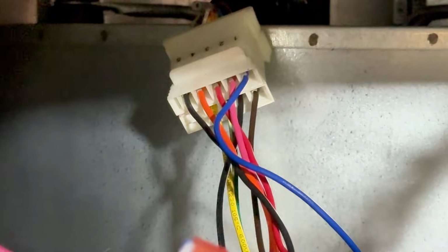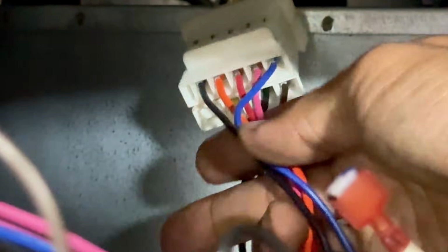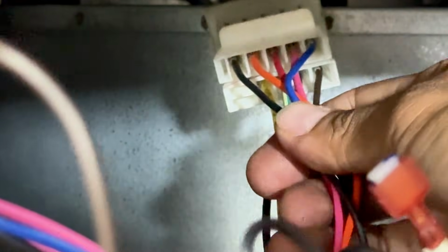So if you were to look at that carefully there, you have this connector right there, okay? Right there. So the top 5 are low voltage. These are my speed taps. If I were to put that out of the way, you see the bottom ones now. My black and my yellow are my 208. That's high voltage. The green one here is my ground, and my brown one is my common 24 volts.